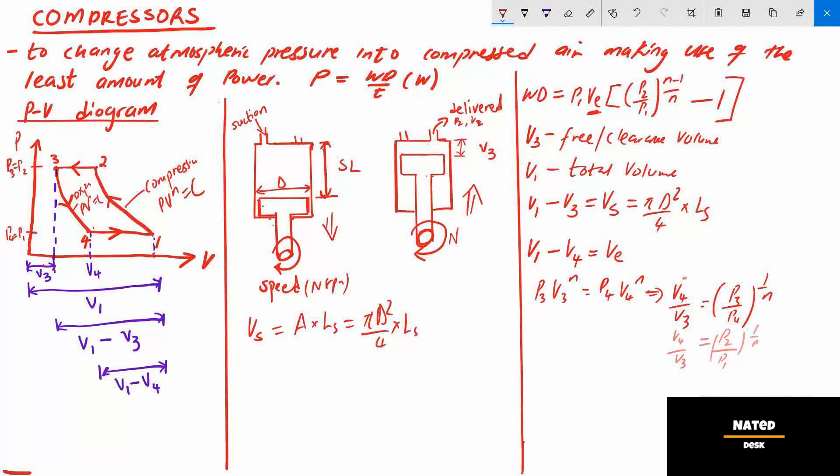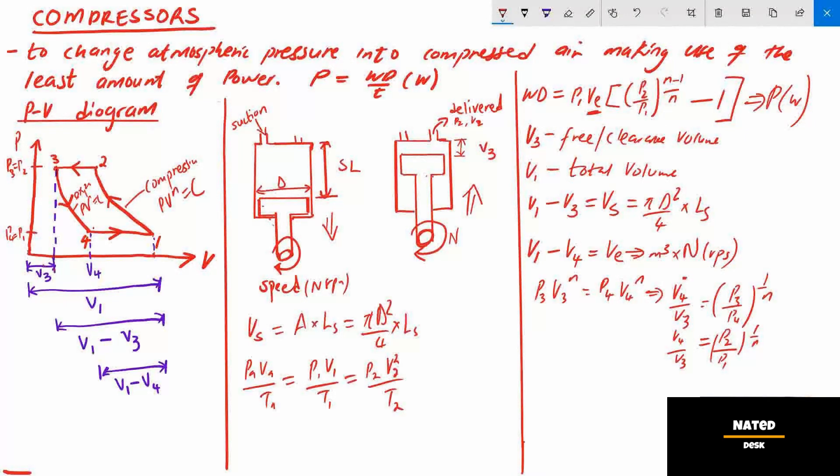Note, when the volume of air delivered by a compressor V2 is allowed to change back to atmospheric temperature and pressure, it is what we refer to as free air delivered, FAD. Thus we have the following formula: PA times VA divided by TA is equal to P1 times V1 divided by T1, is also equal to P2 times V2 divided by T2.